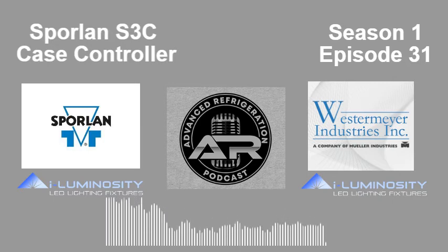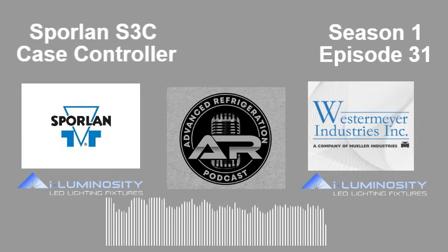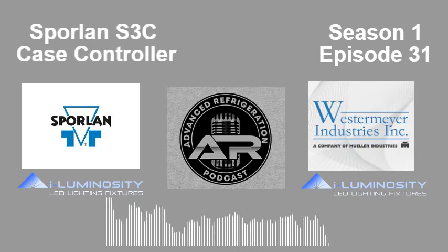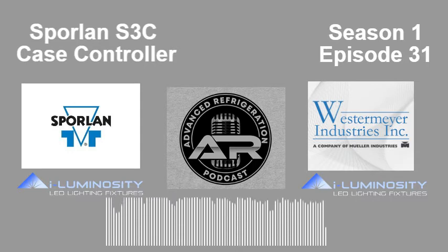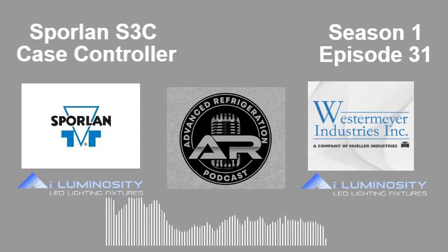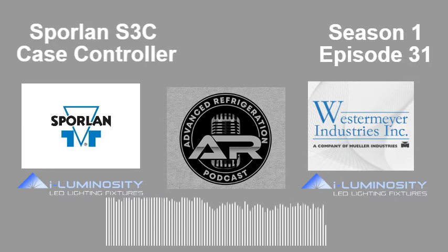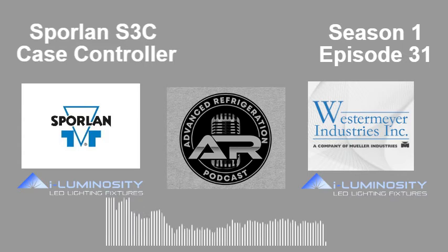They're there, just like the humidity sensor as well, which works in conjunction with all of that. But folks seem to be more focused on the defrost and controlling the pulse width modulating valve or the EEVs, and probably the lights. Those seem to be the big hitters, that folks are concerned are functioning properly and making cold product. That's a question that comes up: everything's running, but we're not getting cold enough, or not getting cold at all. Are the compressors running? Have you actually laid eyes on anything? That comes into play as well.